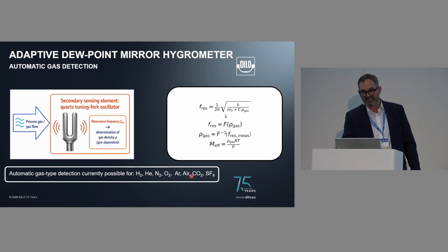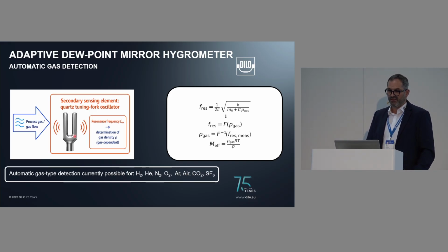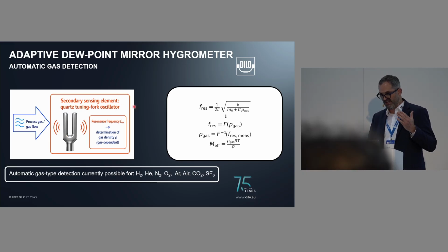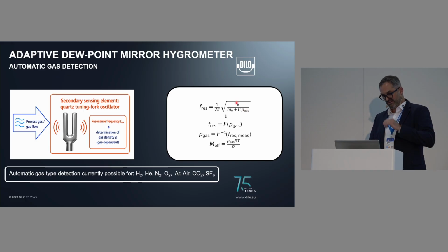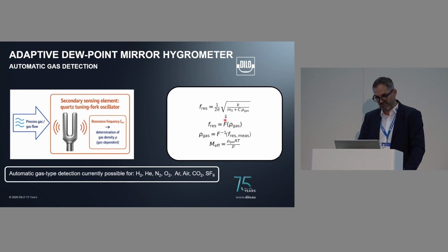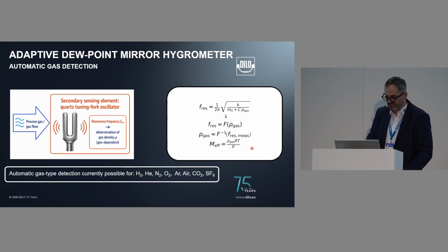So how does the automatic gas detection work? We have here a quartz tuning fork oscillator. It oscillates at a specific frequency, and the equation is here on the right-hand side. And this depends on the density of the gas. And by calibrating the frequency with gases of different densities, you can relate the measured frequency to a gas density, and then using the ideal gas law, or you can also use real gas equations. For example, here the ideal gas equation, and by measuring simultaneously the temperature and the pressure, you get a molar mass.